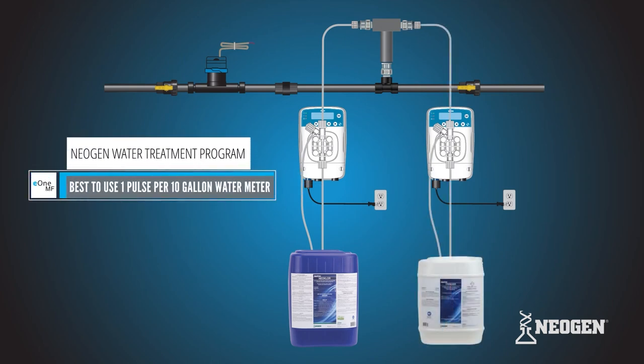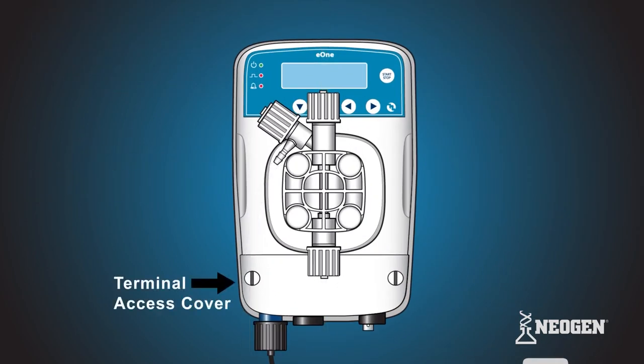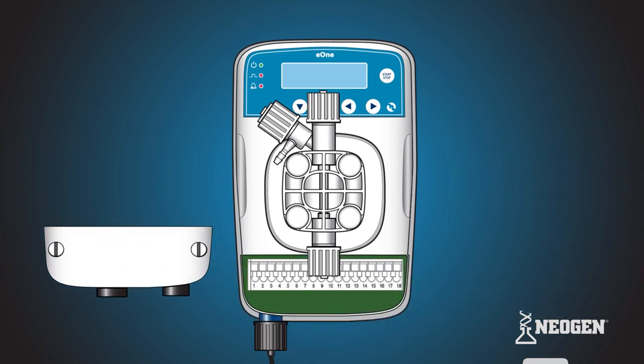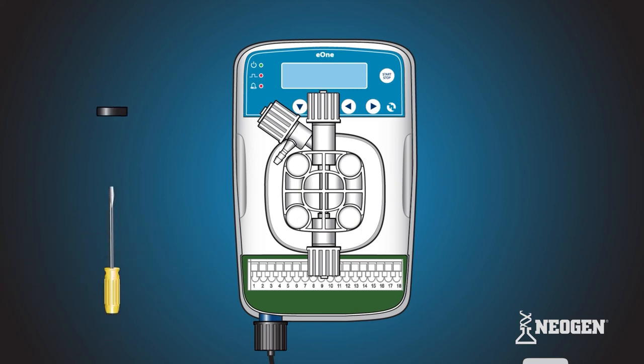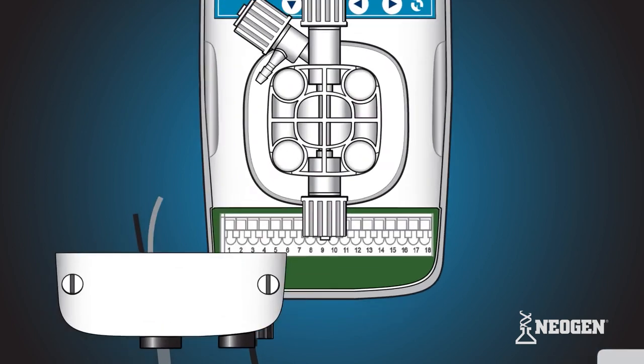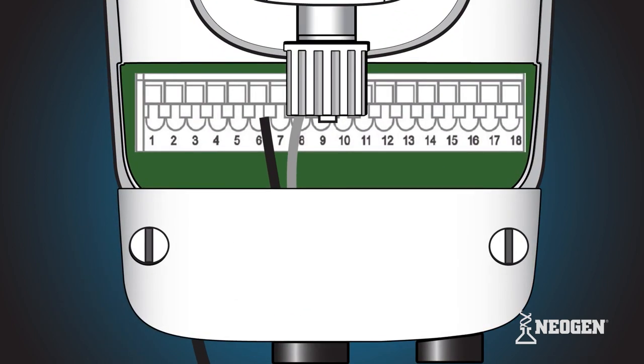Now that your second pump is installed, it is time to connect your pumps to the water meter. Locate the terminal access cover on the eOne MF. Use a flat blade screwdriver to loosen the screws and remove the cover. Locate the left rubber grommet on the bottom of the cover and remove it. Set the terminal access cover aside. Use a punch tool or the narrow flat blade screwdriver to poke a hole through the bottom of the rubber grommet. Grab one of the two-conductor wires and push one end of the wire up through the rubber grommet. Then run the wires back through the hole in the terminal access cover and reinsert the rubber grommet. Pull up enough wire to be able to make connections to the terminal board.